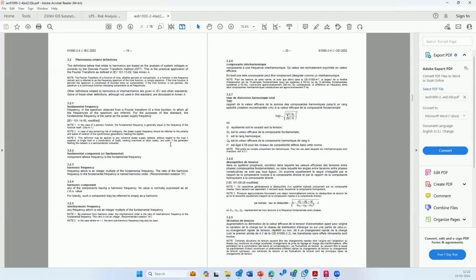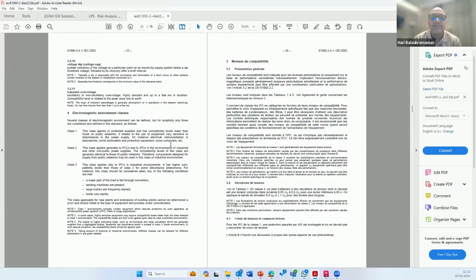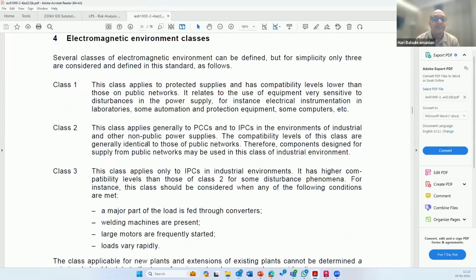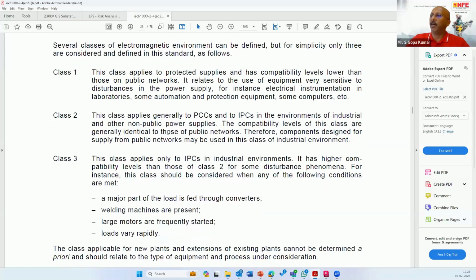I think it's already mentioned in one PPT, class 1 means sensitive load. Yeah, here it is, the explanation of class 1, class 2, class 3. Class 1 applies to protected supplies and has compatibility levels lower than those on the public network. It relates to the use of equipment very sensitive to disturbances in the power supply, for instance, electrical instrumentation in laboratories, some automation and protection equipment, some computers, etc. Class 2 applies generally to PCCs and IPCs in the environment of industrial and other non-public power supplies. The compatibility levels of this class are generally identical to those of the public network. Therefore, components designed for supply from the public network may be used in this class of industrial environment.